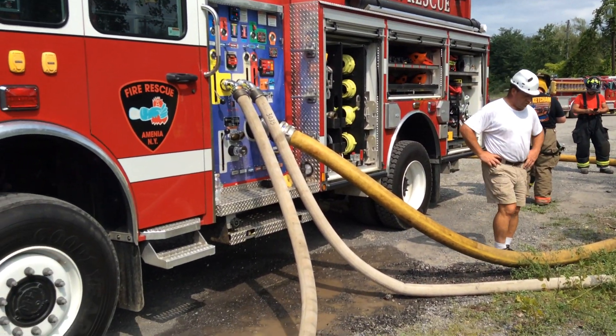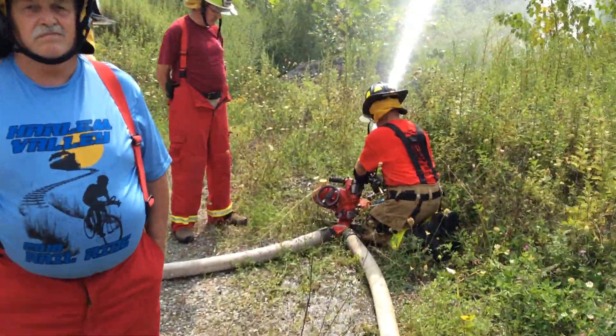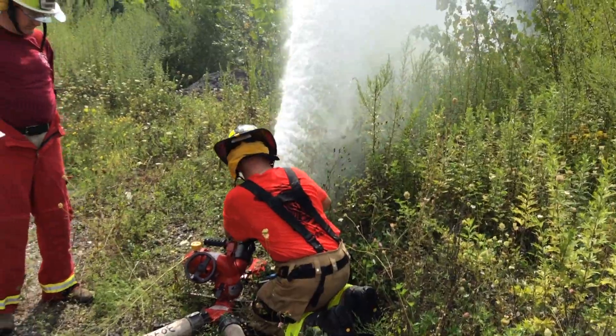This is the first test, no pump engaged, and he gets 651 gallons a minute — 651 — which is through 5,000 feet of 5-inch hose.